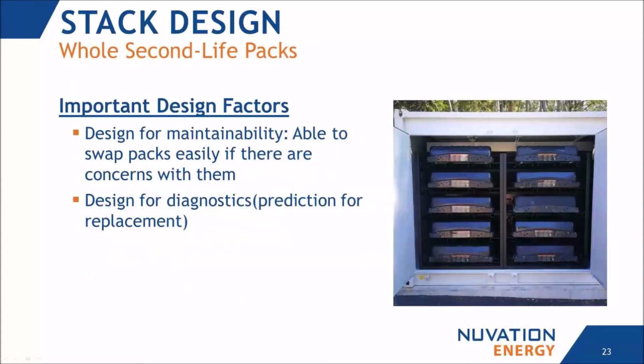So just to reiterate, a couple important design factors when looking at these packs: you have to design for maintainability - you have to be able to swap these packs out easily if there are any concerns with them. You also have to design for diagnostics and predictive replacement, which lends to state of health estimation. You need metrics that can identify cell condition, and Nuvation continues to invest in algorithms and predictions for that. But because we're using the pack, we're separated from that, and you have to rely on the manufacturer's own diagnostics.